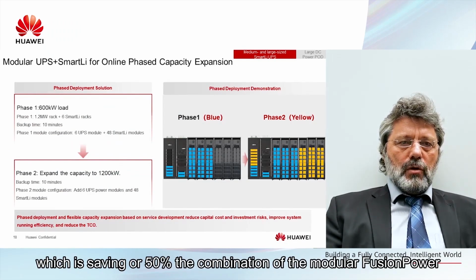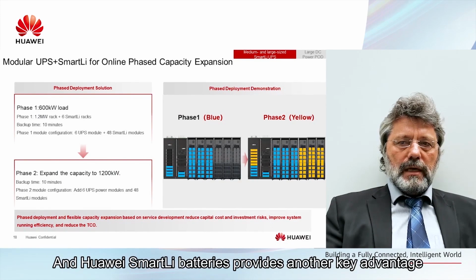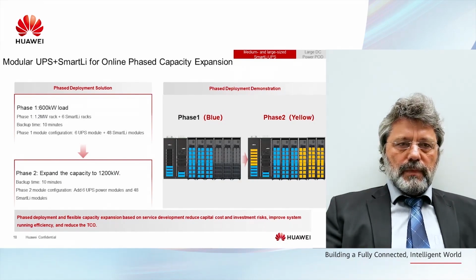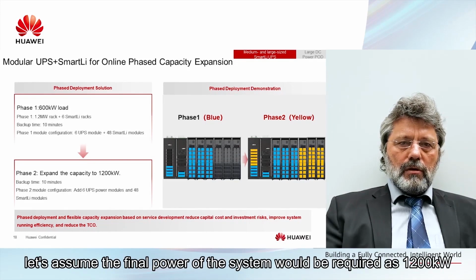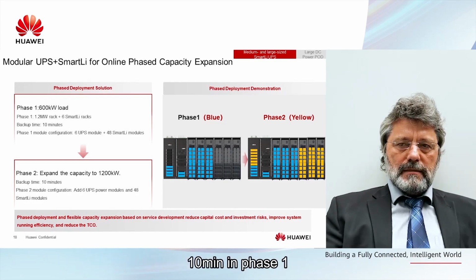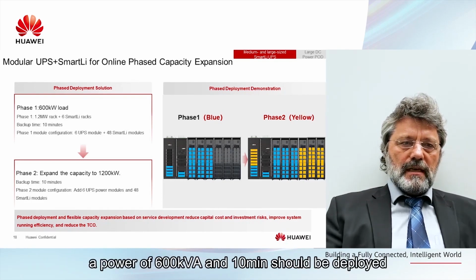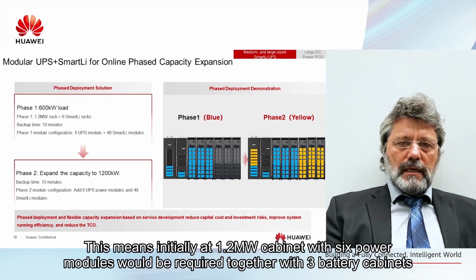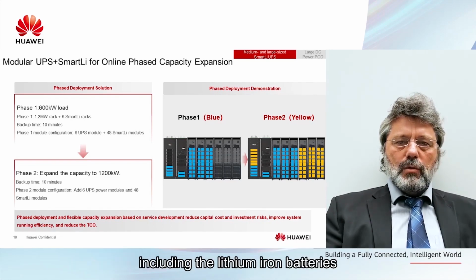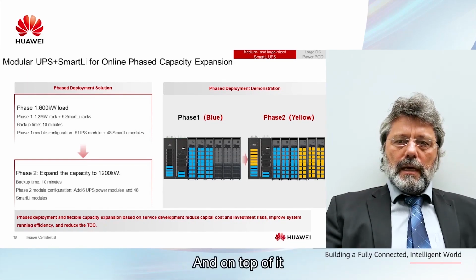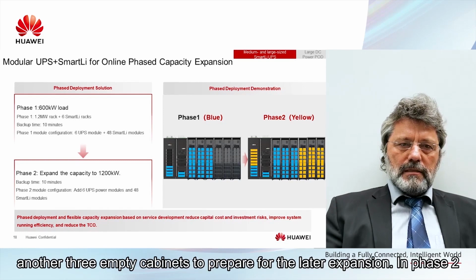The combination of the modular Fusion Power and the Huawei SmartLi batteries provides another key advantage. Let's assume the final power of the system would be required as 1200 kilowatts 10 minutes. In phase 1, a power of 600 kVA and 10 minutes should be deployed. This means initially a 1.2 megawatt cabinet with 6 power modules would be required, together with 3 battery cabinets including the lithium-ion batteries, and on top of it another 3 empty cabinets to prepare for the later expansion.